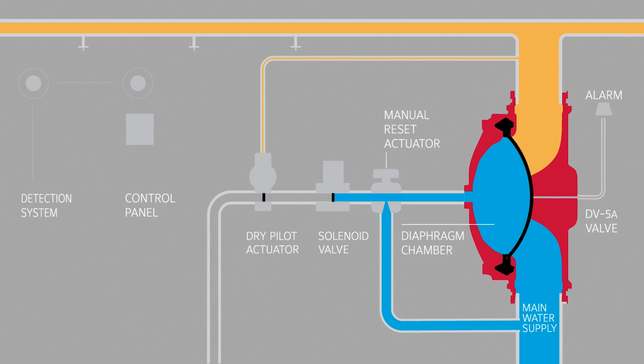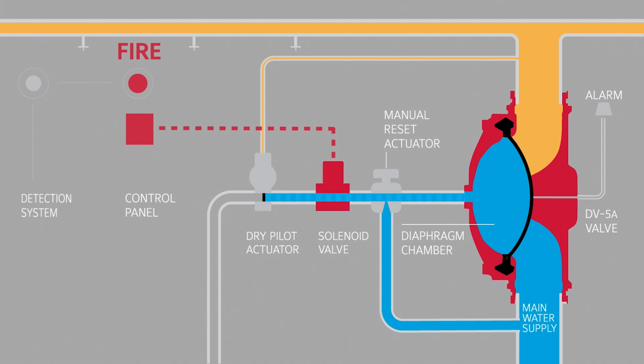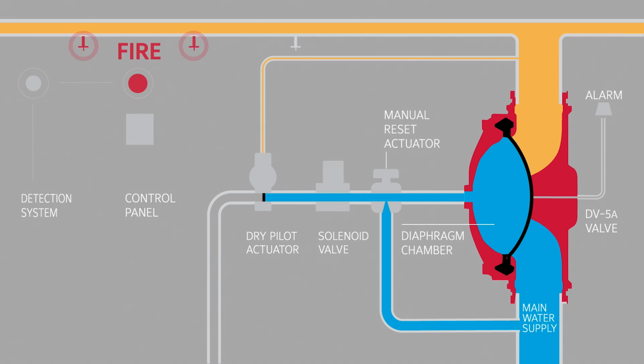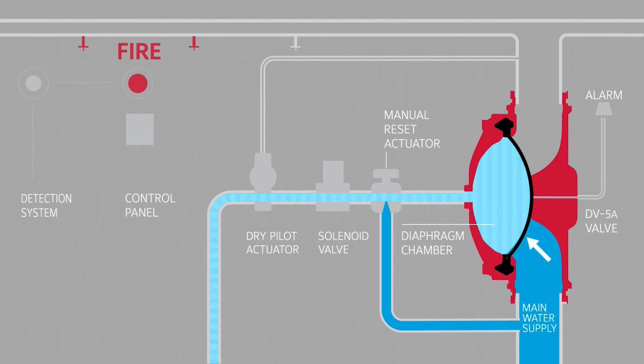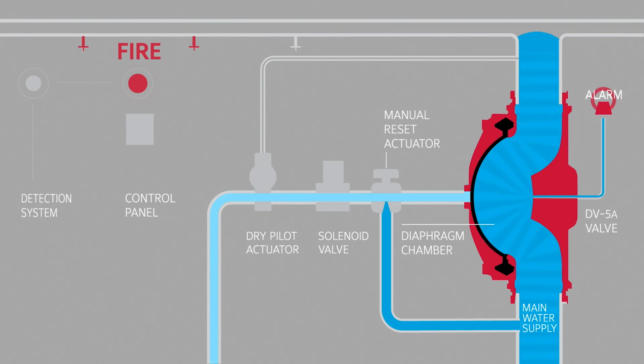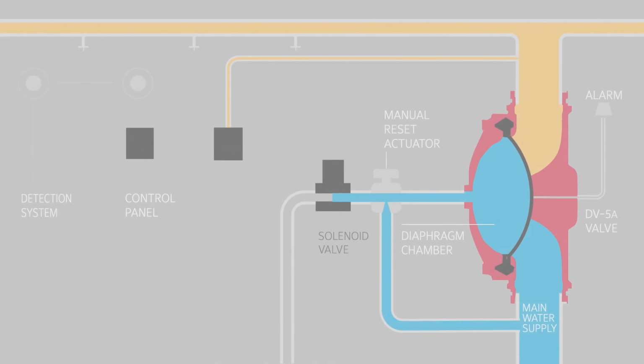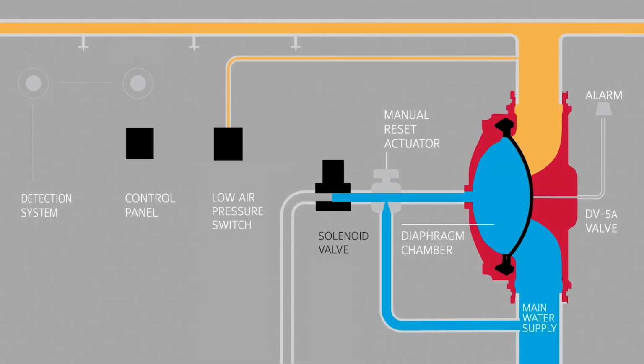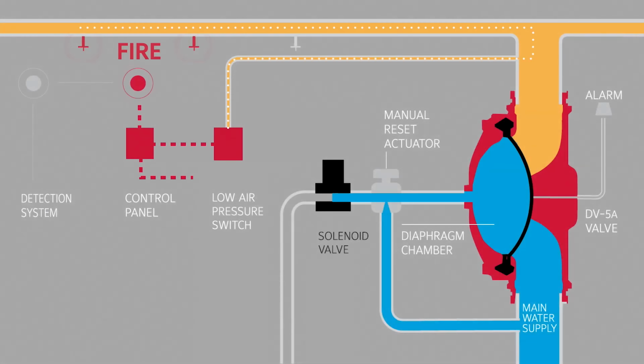The double interlock requires two events to occur for the system to discharge during a fire. First, the electric detection system senses smoke, signaling the solenoid valve to open. Second, the automatic sprinkler heads will burst due to heat. The loss in air pressure opens the dry pilot actuator, releasing water from the diaphragm chamber. The higher pressure from the main water supply pushes the diaphragm open, activating the alarm, allowing water to flow to the sprinklers and suppressing the fire. Tyco also offers a double interlock electric-electric option, which combines heat detection with a low air pressure switch to activate the system.